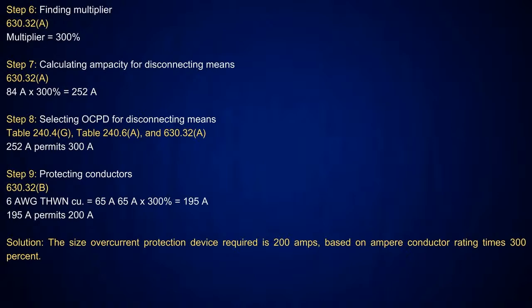So here's 300 amps. Now, if I look at protecting the conductors, if I took that 65 amps at 300%, that gives me 195 amps. The next standard size above that is what? 200 amps. So instead of putting a 300, I could drop down to the next standard size below that 252 amps. I could have gone to a 250, or I could protect the conductors based on the 300%, which is what? A 200 amp. See the difference there? Most people would go to a 250, but you actually could go to a 200 here.